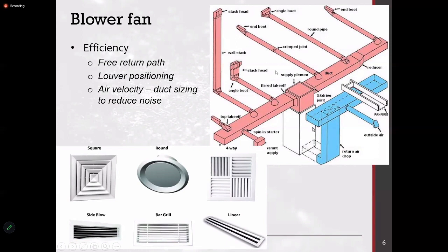So of course you have to ensure at this intake you have sufficient filters, insect filters, etc., and ensure they are cleaned at frequent intervals so that you can take the intake. So the return path has to be clear. Otherwise, not only the blowing path, most of the time we are only concerned about the air supply, but air suction also has to be quite clear.